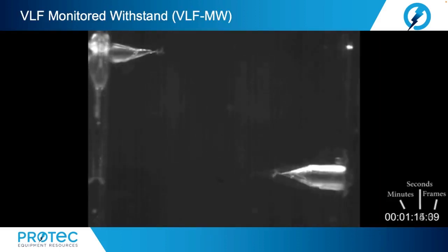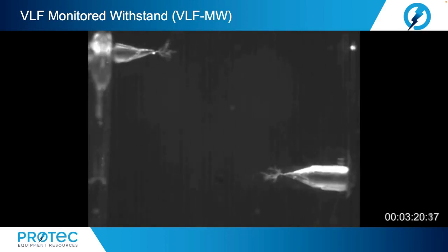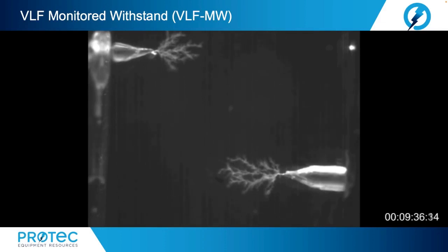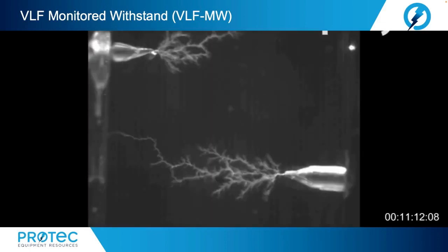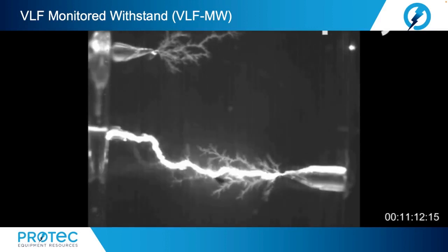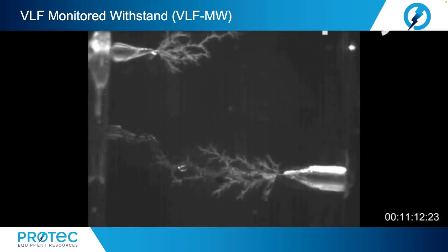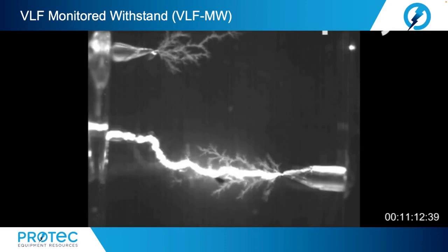Now that we have a better understanding of tan delta testing and the diagnostic value that it offers, let's look at how tan delta could improve the VLF high potential or the withstand test. A monitored withstand is performed by monitoring the tan delta or possibly partial discharge values during the duration of the withstand test period. If partial discharge and discharge channel growth activity is initiated during the test, the growth can be monitored so that the cable is not placed back into service in a weakened state.